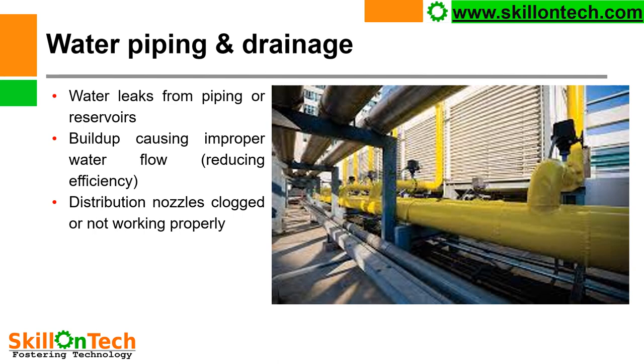Water piping and drainage — you can see a picture of a return header to the cooling tower. Problems generally observed include water leaks from piping or reservoirs, build-up causing improper water flow and reducing efficiency, and distribution nozzles that are clogged or not working properly. All these problems may be inspected and attended to in order to improve the cooling tower water piping and drainage system.